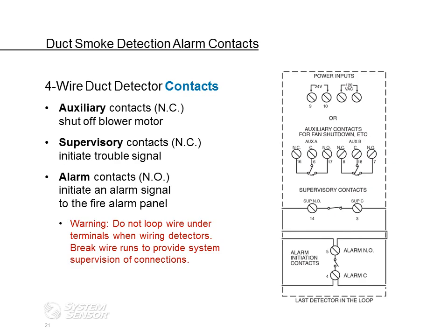This next slide basically just shows you the contacts. It's an exploded view of terminal designations on the control board side. Four-wire duct detector contacts, we have auxiliary contacts. Those are normally closed. That's used to shut off a blower motor or a fan, or depending on how you're shutting down the system, line voltage, however you're doing your shutdown. Supervisory contacts, those are used to initiate a trouble signal to your remote test accessory or to a fire panel. And then alarm contacts are used to initiate an alarm signal to the fire panel.